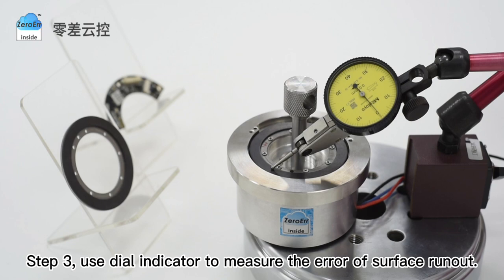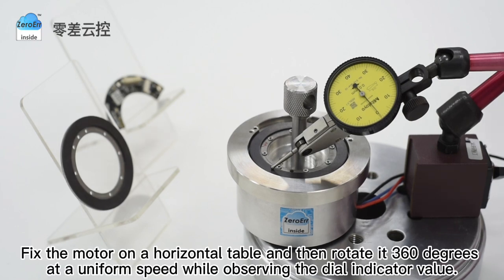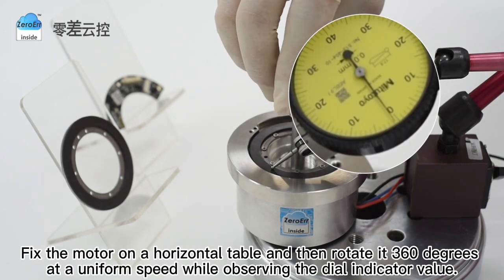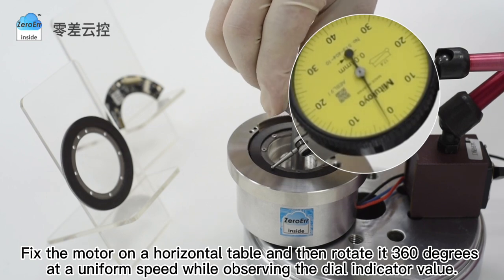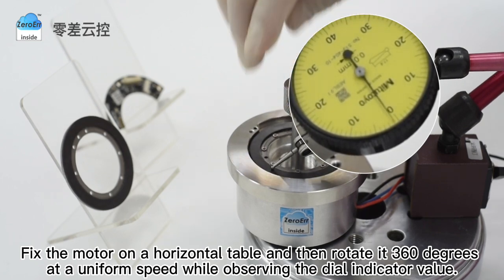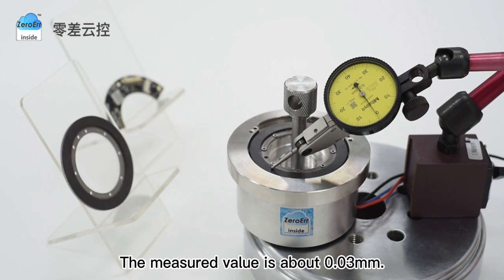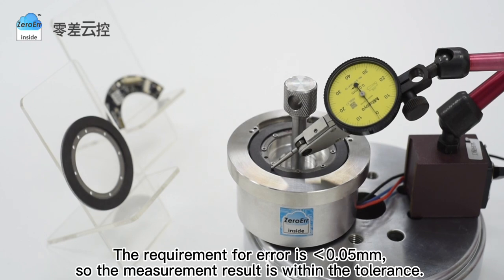Step 3, use dial indicator to measure the error of surface runout. Fix the motor on the horizontal table and then rotate it 360 degrees at a uniform speed while observing the dial indicator value. The measured value is about 0.03 mm. The requirement for error is less than 0.05 mm, so the measurement result is within the tolerance.